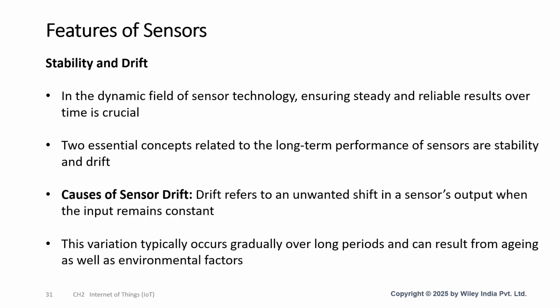Stability and drift: in the dynamic field of sensor technology, ensuring stability and reliable results is crucial, but there can be variations because of drift. Drift refers to an unwanted shift in a sensor's output when the input remains constant. This variation typically occurs gradually over long periods and can result from aging as well as environmental factors, due to the prolonged use of a sensor. So the output is no more stable.